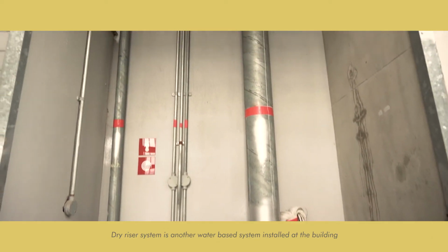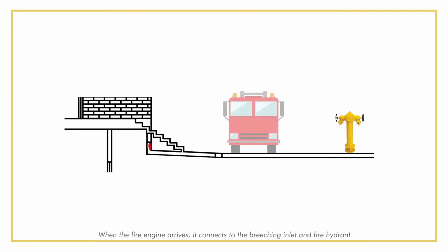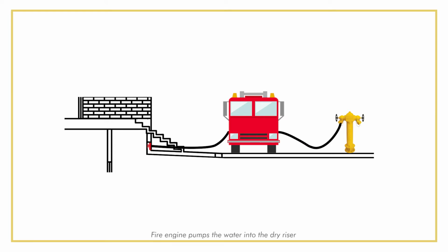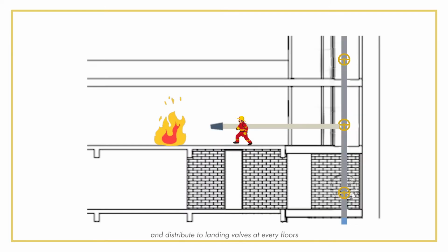Dry riser system is another water-based system installed at the building. When the fire engine arrives, it connects to the breeching inlet and fire hydrant. The fire engine pumps the water into the dry riser and distributes it to landing valves at every floor.